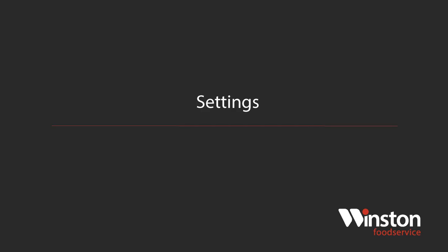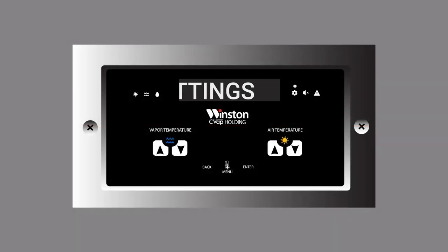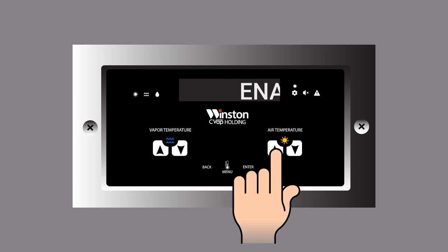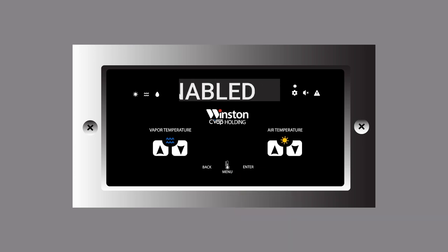Settings menu. Security. This setting allows the user to lock the unit, so settings cannot be changed. From the settings menu, select Enter. Security will be displayed. Select Enter. Disabled should be displayed unless the security lock is currently enabled. To enable the security lock, select the air temperature up button until Enabled is displayed.